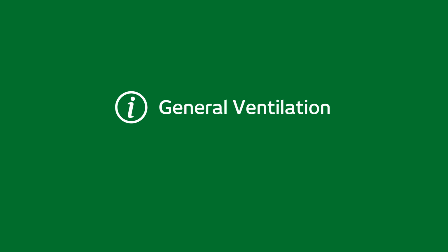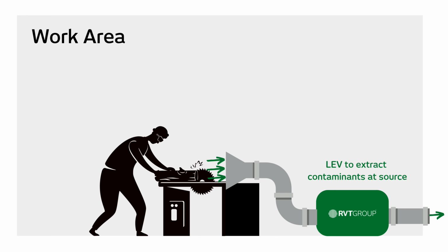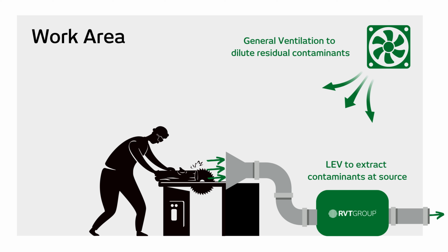In addition to LEV, you might need general ventilation, fresh air being forced into the work area. In many cases, you would need LEV to extract the contaminants at source, but you would also need general ventilation to dilute residual airborne contaminants.